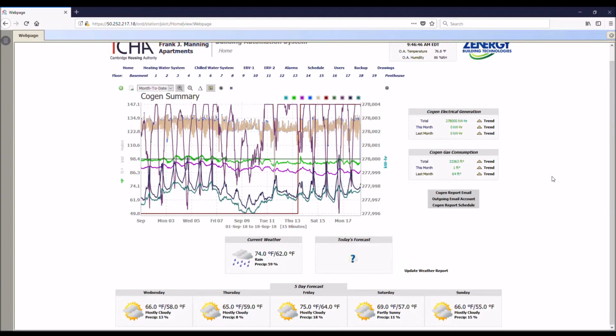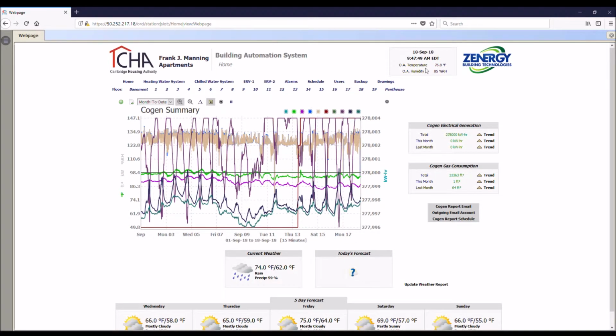It's a black box that we refer to as a JACE. The manufacturer and product is Tridium Niagara, so this is all a Niagara-based system, pretty standard. This is currently N4 - a couple years ago they released this new version, which has all HTML5 graphics and some updated security features. We just updated the version to 4.6, which it was licensed for, so that's currently what we're running. Just a really user-friendly interface overall.